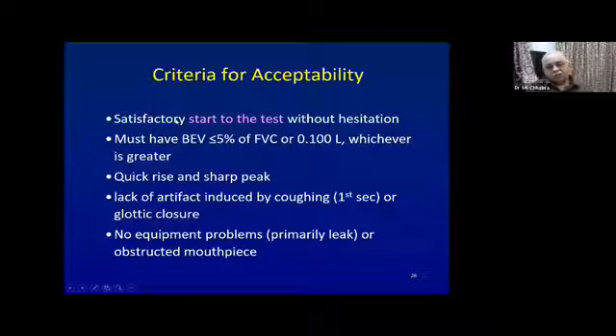So the current criteria is that the start of the test. In one of the earlier slides on the flow volume curve, I had stressed that there are 3 important points to look for. One is the start of the test, that is when the patient has reached the total lung capacity. So immediately from that point, the patient must exhale out fully. If the patient has slight hesitation at total lung capacity, there is a small leakage of air. So that is measured by a process called back extrapolation. This is measured by the software, and usually it will display in the results what the patient's back extrapolated volume is. So the acceptable back extrapolated volume is 5% of the vital capacity or 100 ml, which means that the initial hesitation led to loss of this much volume. So this will be removed from the vital capacity.